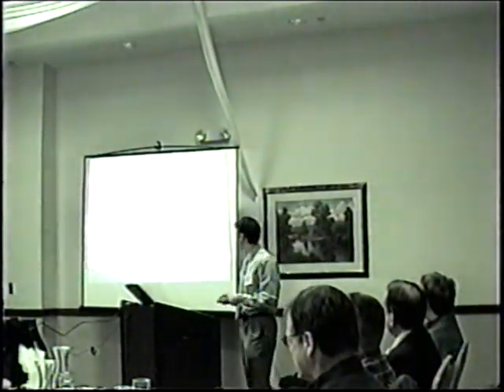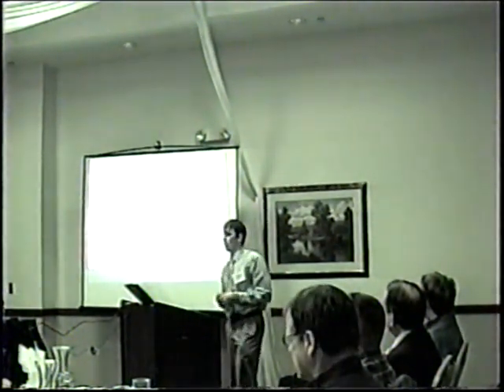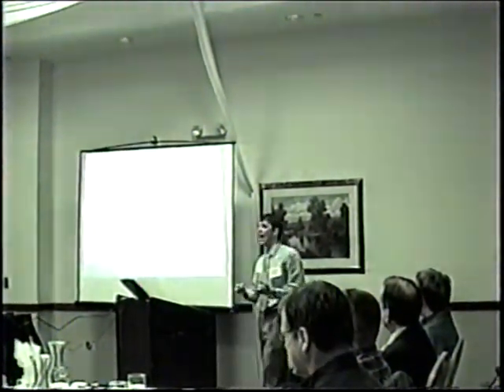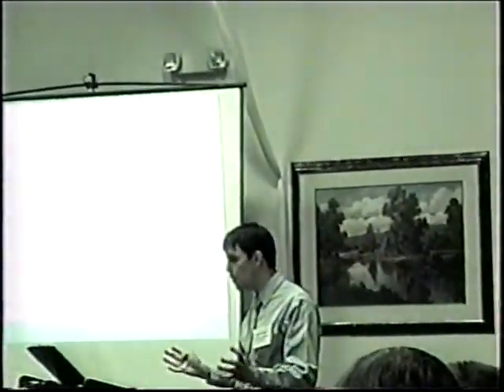That seems like reasonable criteria. When they ran all the tests they ran, they came up with their revised pass-fail criteria. And I'd say it did not come from a proactive determination of what pass-fail should look like. It was, we have all this data, we better figure out how to make some of this stuff look like it worked. They said the fire did not extend beyond the first row of commodity in the target array. And we'll have some pictures of it exactly. I mean, you can burn on the target array all you want, as long as you don't burn all the way through the target array, that was okay.